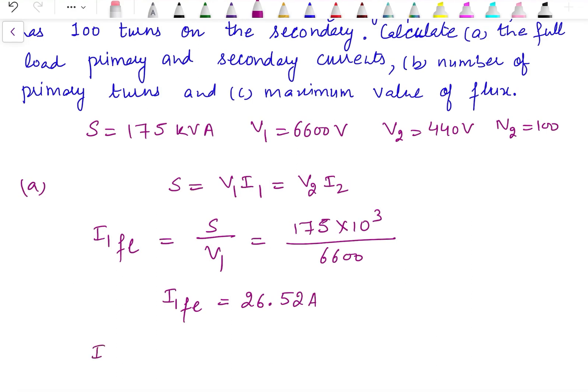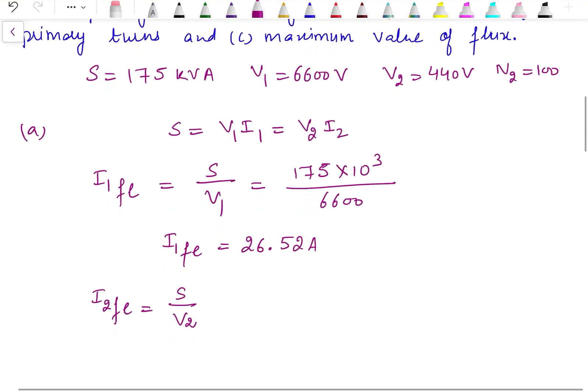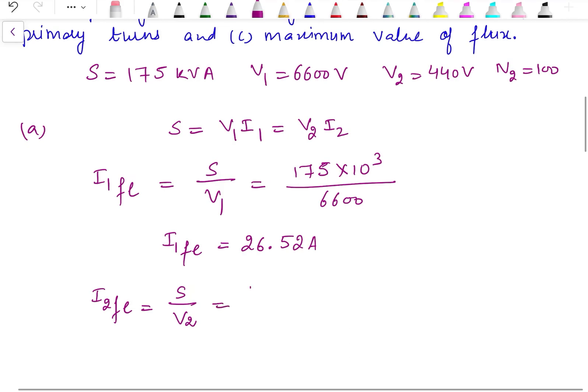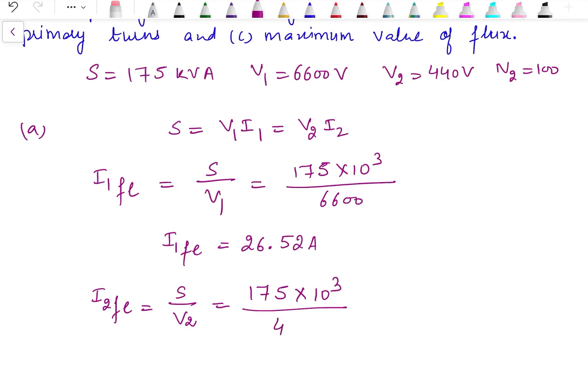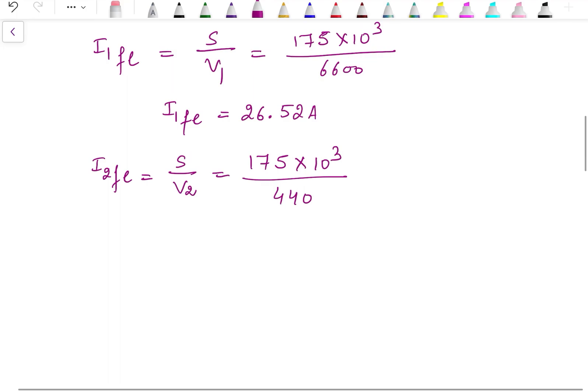Similarly, we can calculate the full load current on the secondary side, which is equal to apparent power divided by the secondary side voltage: 175 × 10³ / 440. So the full load current on the secondary side is 397.73 amperes.